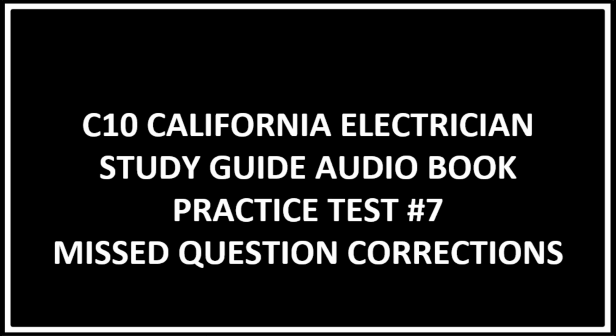Question 51. Minimum trade size of liquid flex non-metallic conduit is ½ inch. Non-metallic flex, ½ inch. Smallest size LFMC, metallic is 3/8 inch.